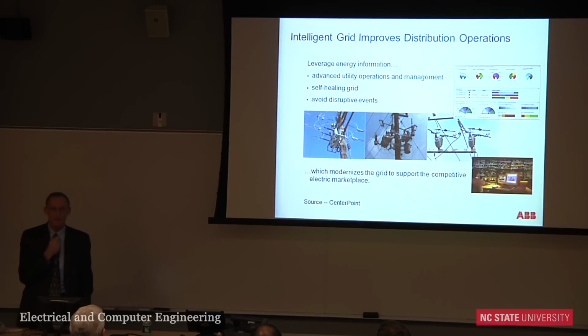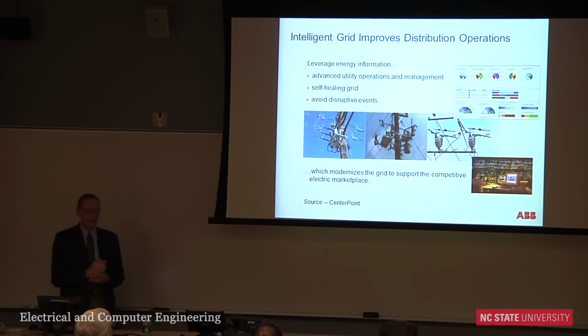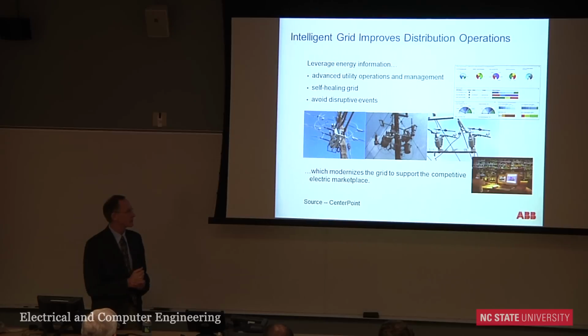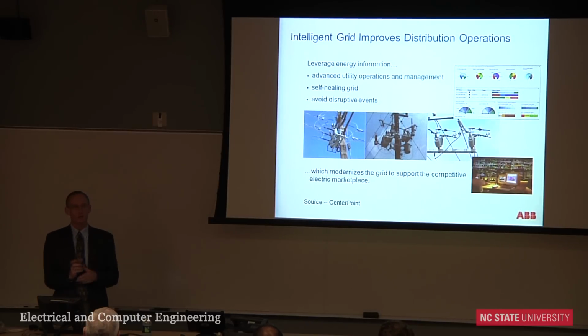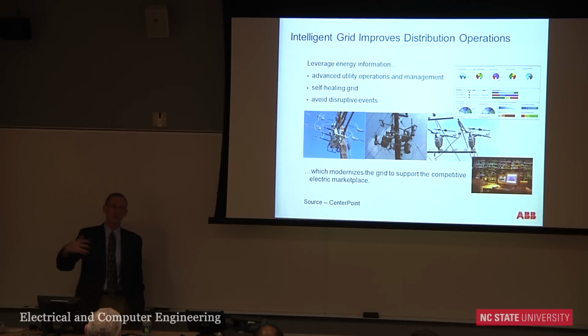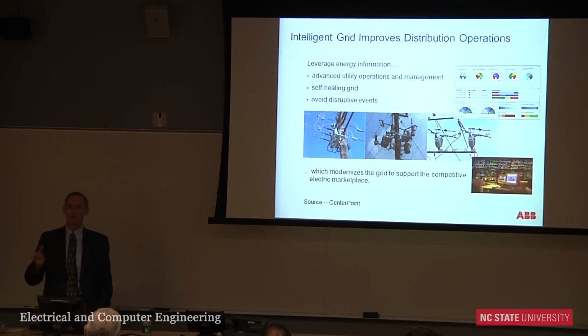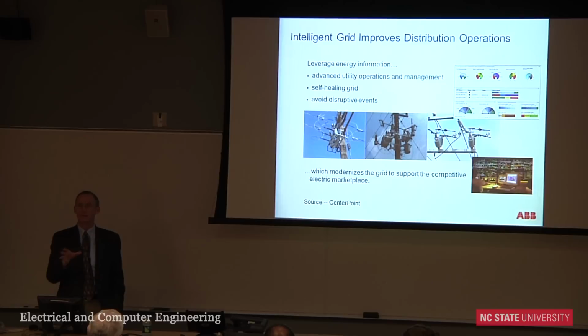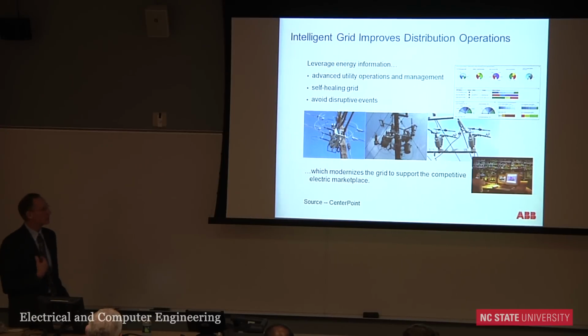This is a slide from CenterPoint. CenterPoint is implementing a distribution management system and also an AMI, or what they call AMS, Advanced Metering System. They're putting reclosers out on about 15% of their distribution system, which are communications-enabled, using the AMI system's communications for data backhaul so they can remotely and automatically control these reclosers to isolate faults and restore customers not connected to the faulted section. This project is ongoing right now, and we happen to be the vendor providing the intelligent grid, meaning the reclosers, as well as the DMS software.